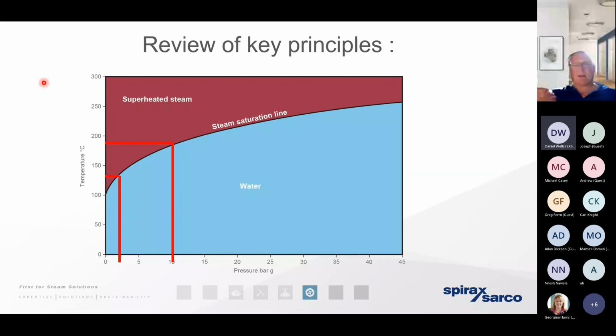So steam actually gives up its energy isothermically. There isn't an exchange of temperature. So that heat loss, the condensate that exists in the distribution pipework, that's actually going to exist at the same pressure and the same temperature as the steam does, and the same at the process. So if we had a steam trap that failed open, the steam pressure could be 10 bar gauge and then falling in pressure very, very quickly to somewhere close to atmospheric. So of course, we're going to see that sudden expansion of the steam. But we're always going to have condensate upstream of the steam trap as well. So if the condensate exists as a single phase liquid, 10 bar gauge, 184 degrees, as that condensate falls in pressure, it can no longer exist at the same temperature. It can only exist at a temperature of 100 degrees at atmospheric. So it's got to cool down very, very quickly in a short space of time.